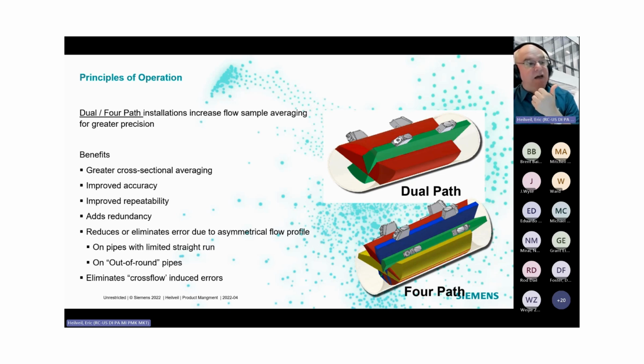So if you had a slight bend in the pipe, if there was a disruption because a valve was left half open, or you had a reducer or an expander somewhere around, and the flow profile wasn't just perfect, having all of this extra coverage with just dual beams, doubling the amount of information you can pull off the pipe, can help correct for an awful lot of flow variations. 4 paths puts almost 80% of the flow in that pipe under examination. So that's for super accurate or super challenging flow applications.